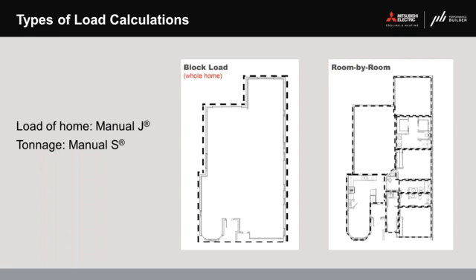The reason we want a room by room load is because that tells us how much air needs to be delivered to each room—how much capacity each room requires, since capacity and CFMs are directly tied. Without that, we can talk about zoning all we like, but it doesn't really make sense; we'd just be guessing about the real needs of individual spaces.